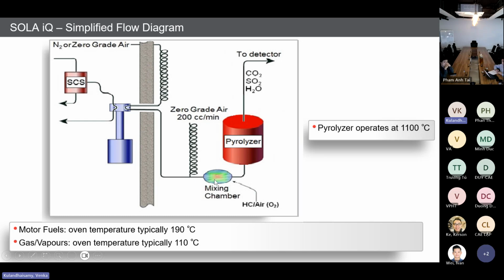After the thorough mixing, the mixed gas will flow through the pyrolyzer. The pyrolyzer is heated up to 1100 degrees Celsius. Due to the temperature, the gas will totally burn and then react with the ceramic tube. And then finally, it will emit three components: CO2, SO2, H2O. The CO2 and H2O are none of our business. So the three components will enter the detector. The detector uses a UV lamp of a particular wavelength. That wavelength energizes only SO2 molecules. Whenever the SO2 molecules de-energize, they emit photon energy. That photon energy is captured by our PMT tube, then it converts the signal to a ppm level, or ppb level, or percentage level of sulfur.